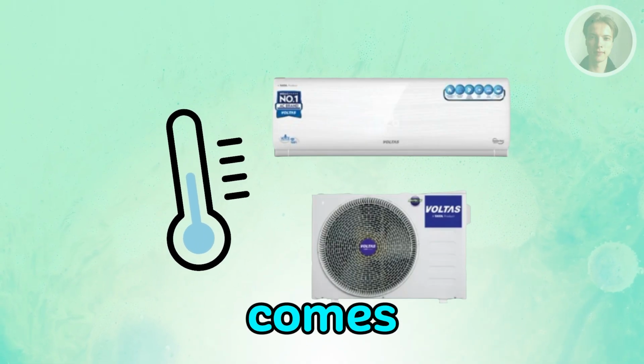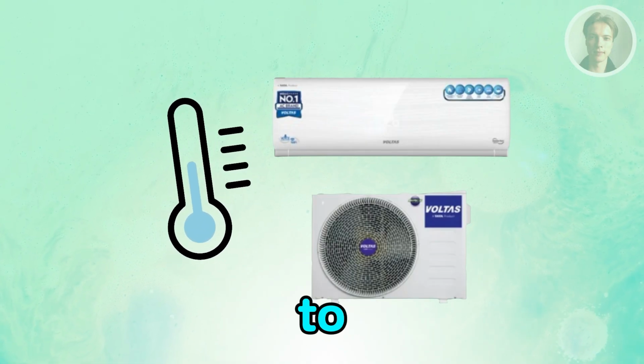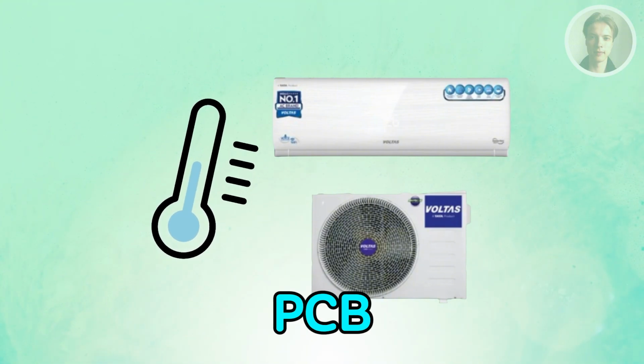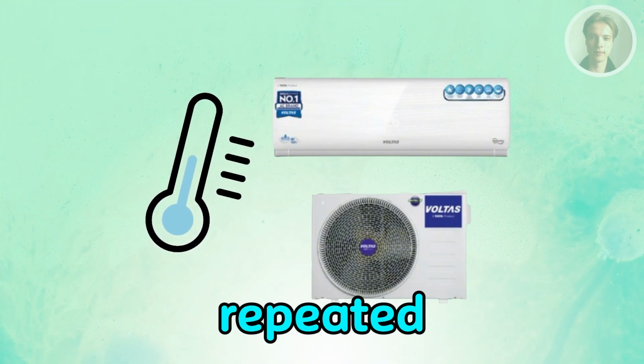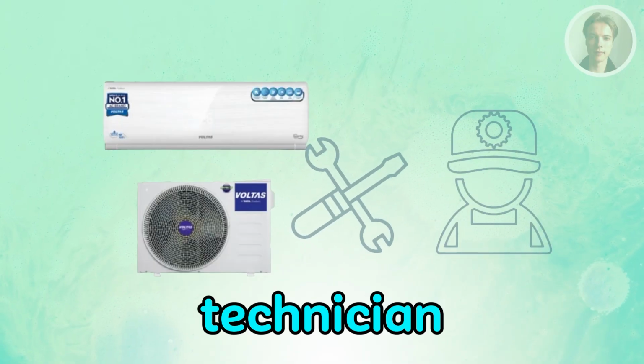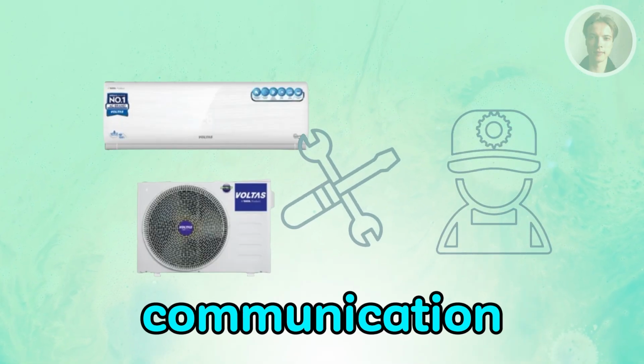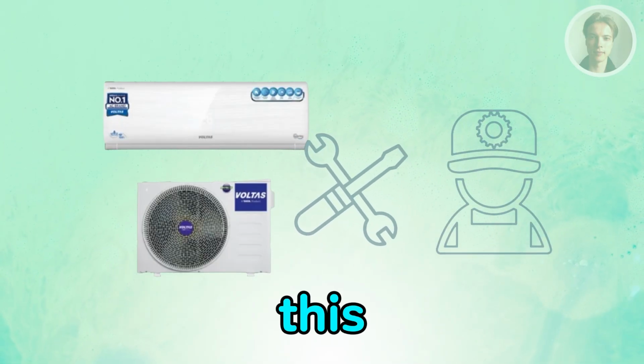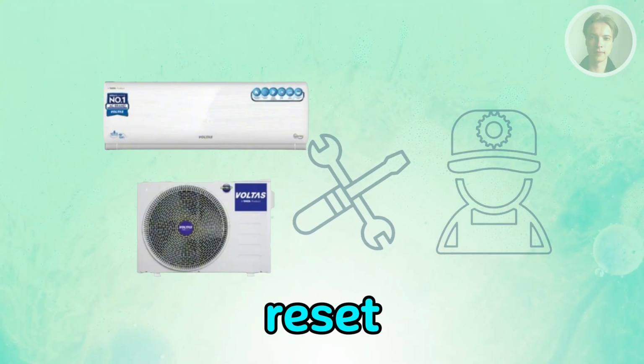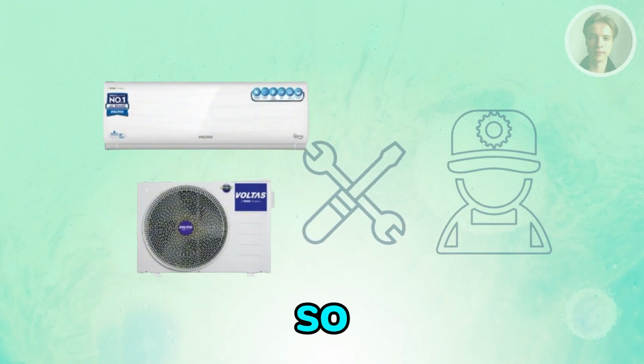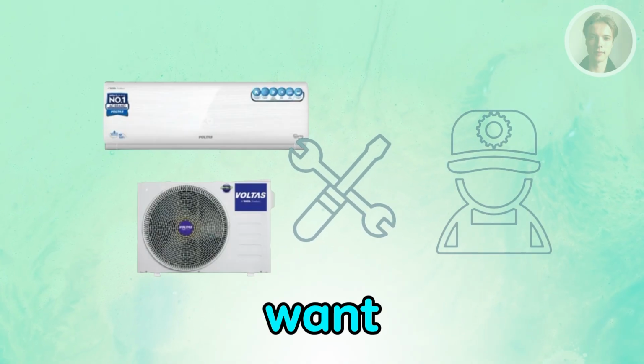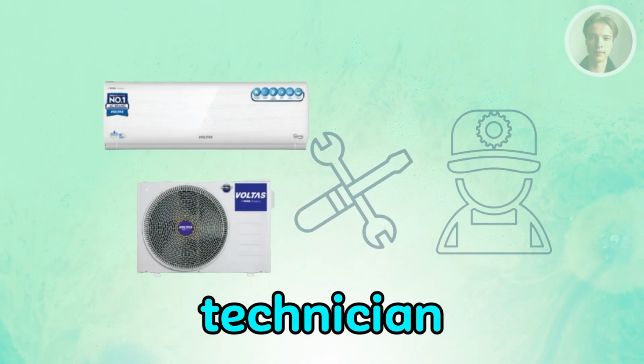Now, if the 5D comes back, it usually points to a sensor warning or a PCB issue. Repeated 5D errors typically need a technician to check temperature sensors, communication wiring, or the control board. At this stage, continuing to reset won't permanently fix it. So you may want to contact a technician for this one.